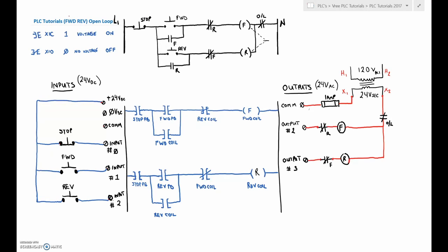What we'll do is we'll go through and address each of our different inputs. So on the Allen Bradley, I have input :0.0. And then there's a slash, a forward slash, and then whatever bit you are looking for. So this guy is going to be bit 0.